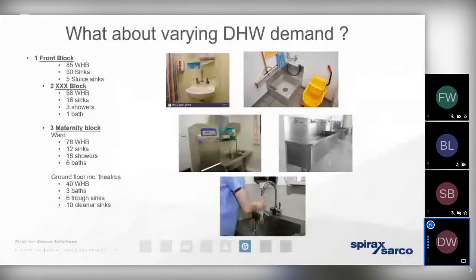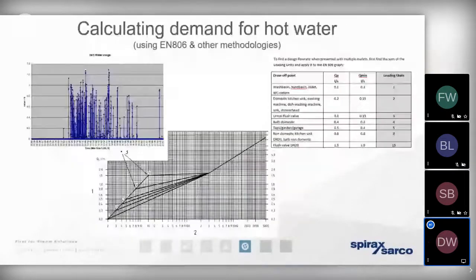So it can be very difficult to accurately determine how much hot water is required and therefore how to size the heat exchanger. So we need to be very clear about how we've calculated the demand for hot water. And in the case of a storage calorifier or shell and tube heat exchanger, it's got a fixed volume on the secondary side. So we've only got one opportunity to get this sizing correct.